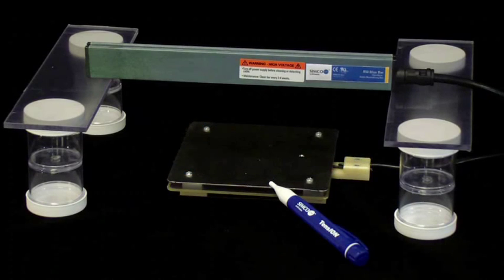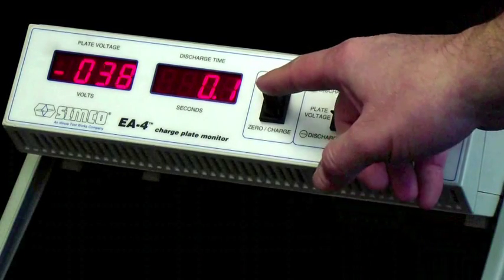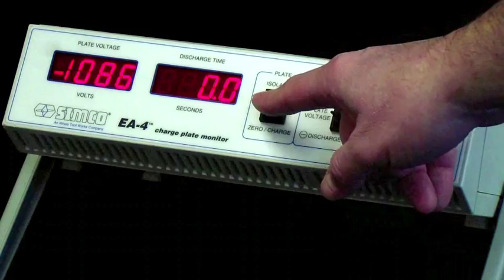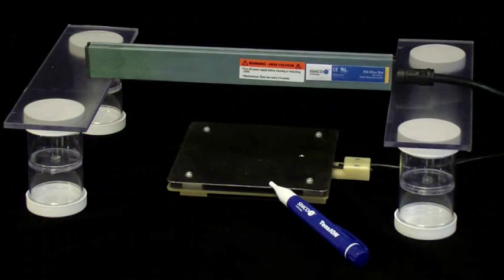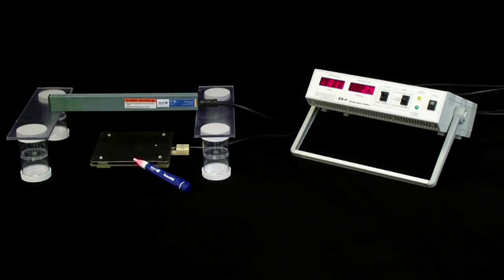In this case, we show a static bar being used to neutralize a charged CPM, and we will note the response of the voltage detector. The CPM is charged up to 1000 volts, as you can see by the display. The static bar is placed over top of the CPM and powered on.